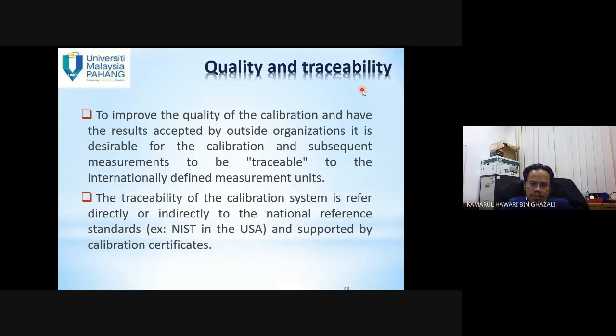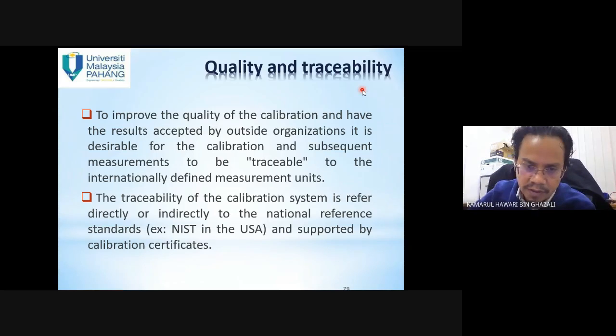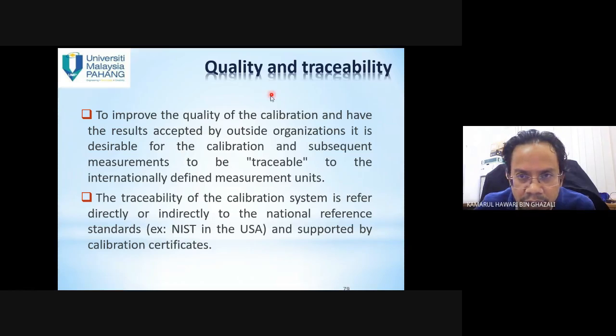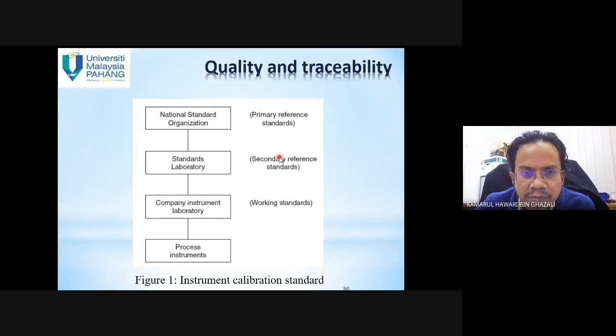It is desirable for the calibration and subsequent measurement to be traceable to the internationally defined measurement unit. So the traceability of the calibration system is referred directly or indirectly to the National Reference Standard, NIST, and supported by a calibration certificate. So this is the quality and traceability. National Standard Organization, Instrument Calibration Standard, National Standard Organization, Standard Laboratory, Company Instrument Laboratory, Process Instrument. So it is not an easy task to do calibration. It must follow a standard.